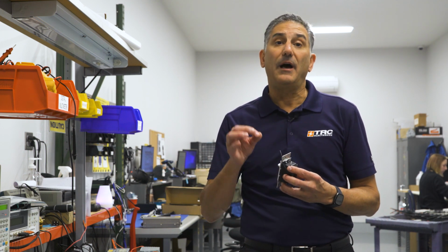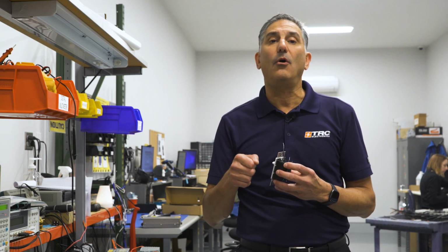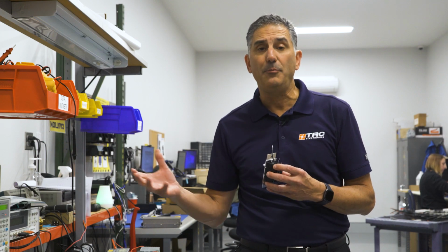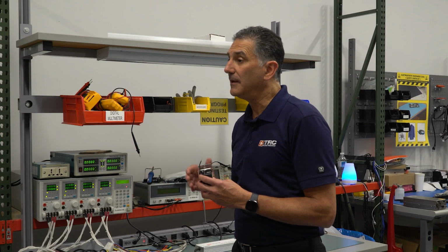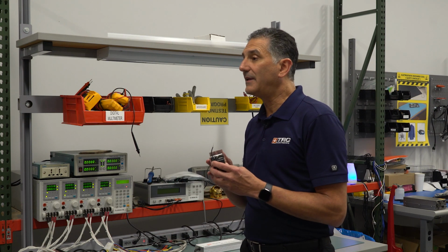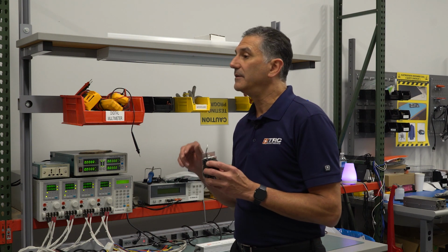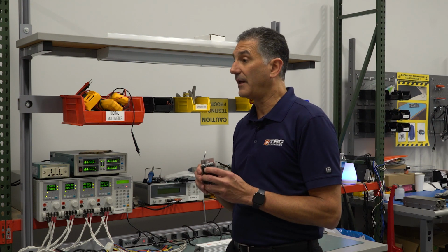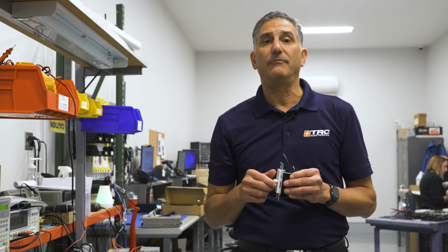For example, a 0 to 10 volt dimmer can actually dim all the way down to zero current or zero light output. We would also describe this as a dim to off function, because when you go down to the lowest setting on the dimmer, the drivers will actually turn off, which means that the LED light fixtures will be off. The next control would be the 1 to 10 volt dimmer.